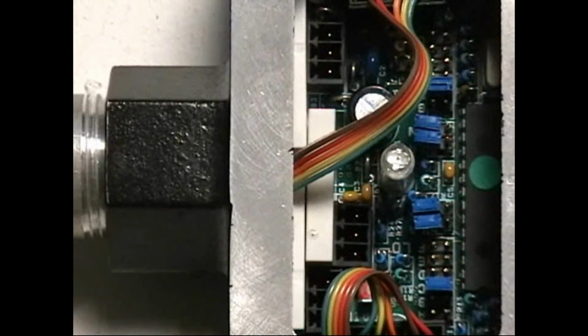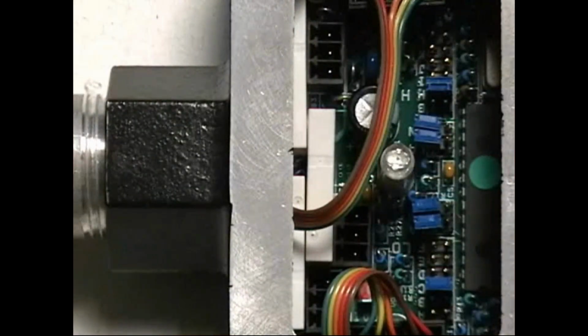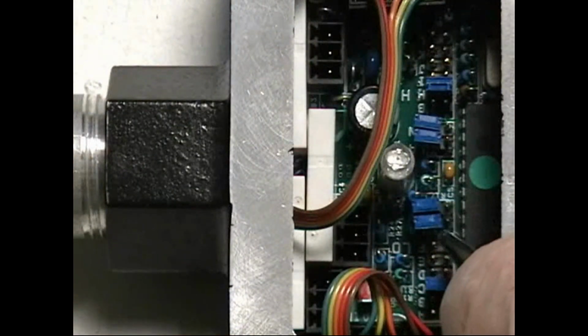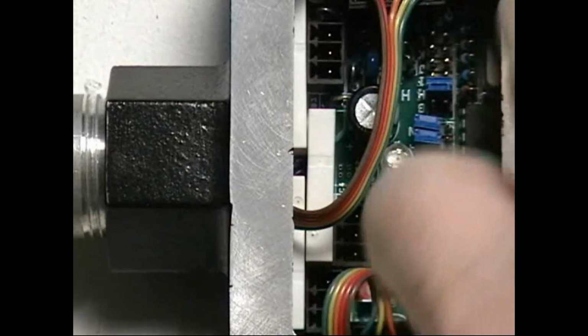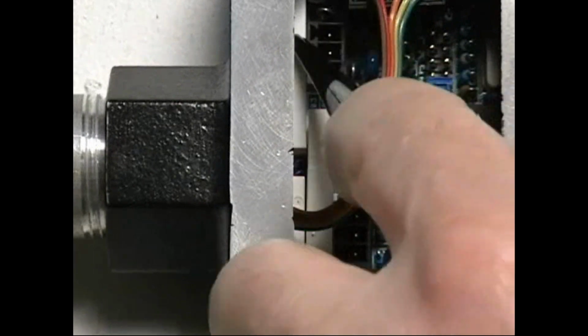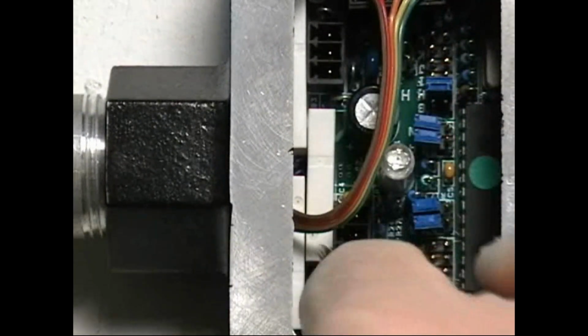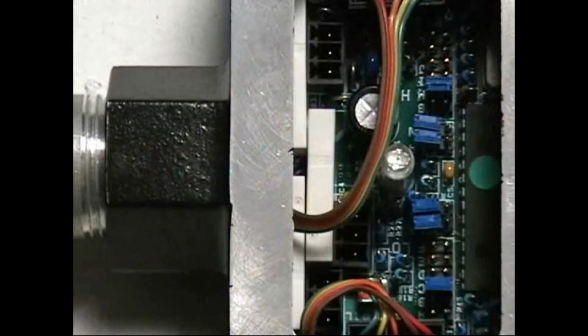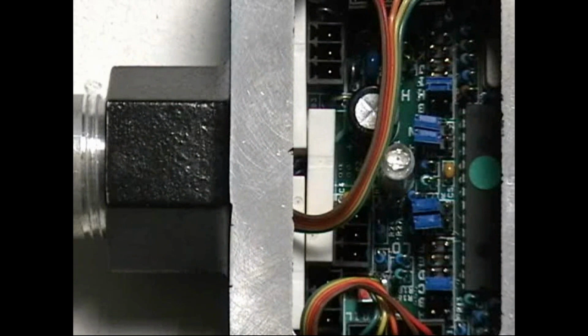Located on the SLAM PC are jumpers that allow you to choose the alarm level, both low alarm and high alarm. The bottom group are for the low alarm. The top group are for the high alarm. There are 3 relays, one for low alarm, one for high alarm, and one for fail alarm, and 3 sockets to wire to these dry contact relays. These relays are single pole, double throw, and rated at 6 amps.